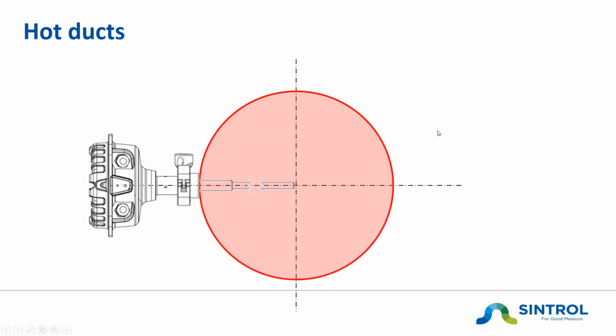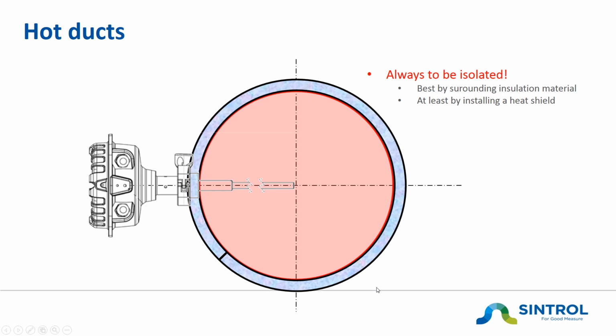Then hot ducts. Well, basically, we have two influences. One is the radiation from the hot duct to the body of the sensor, and the other one is the hot gas inside the duct, which mainly affects our Ryton isolator, which is good for about 200, 250 degrees. So to avoid radiation from the hot duct to our instrument, we either recommend at least a heat shield or, better, a completely isolation around the duct.